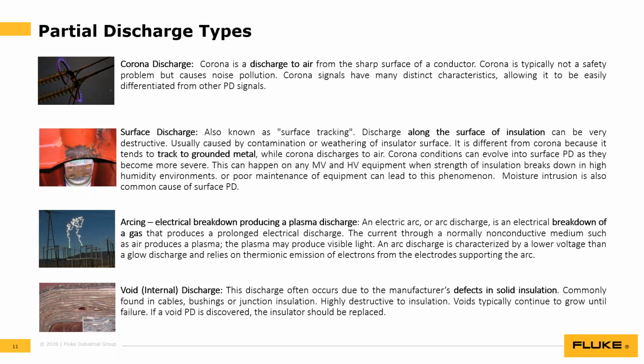And I talked about how partial discharge is really this repeated charge across electrodes. Sometimes that's phase to phase, and sometimes that's to ground. Usually surface discharge is tracking to grounded metal. The other one I'll talk about is void or internal discharge. And this is another one that definitely damages equipment over time. And it's in this insulation material. So it can be insulation that's solid, or it can be gas or liquid insulation, but it's pretty common to find this in cables, in bushings, or anywhere that there's a junction between components that have insulation.